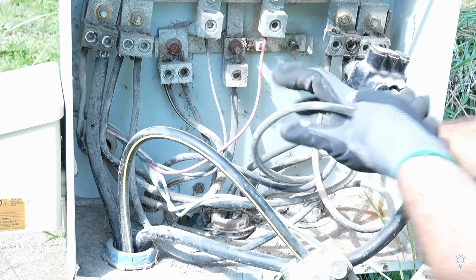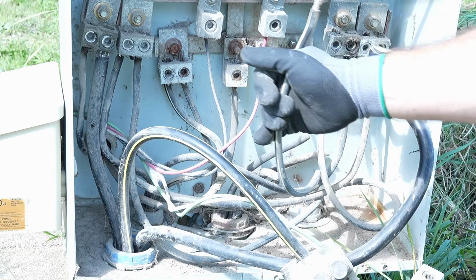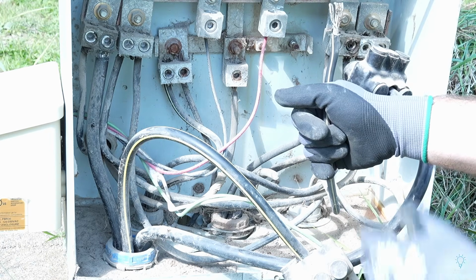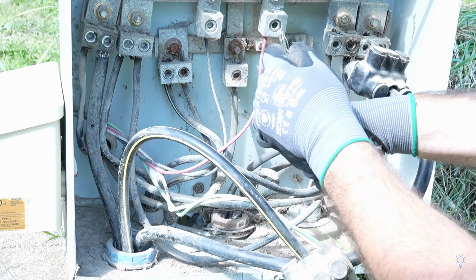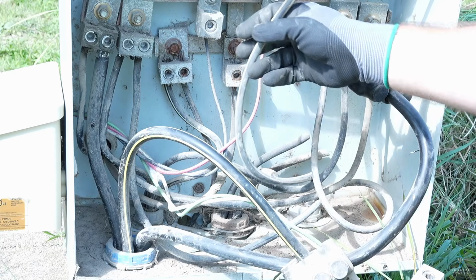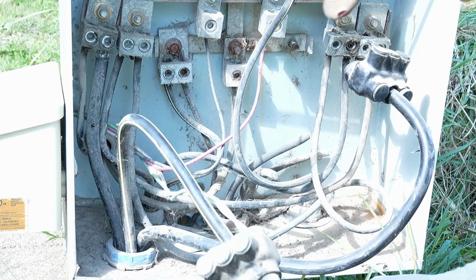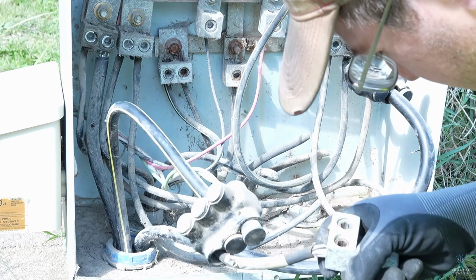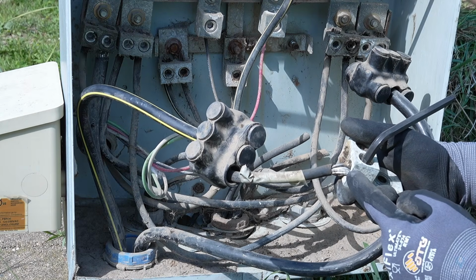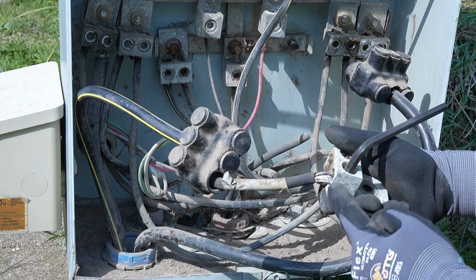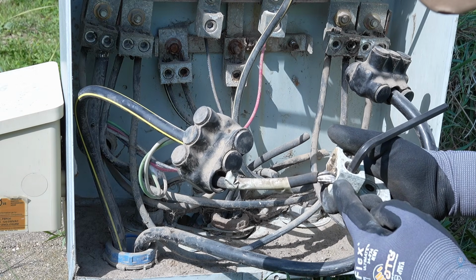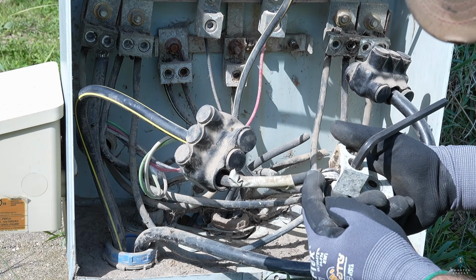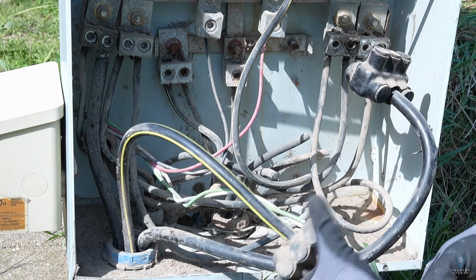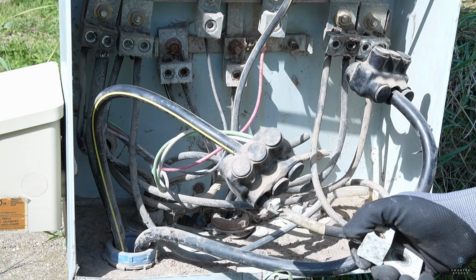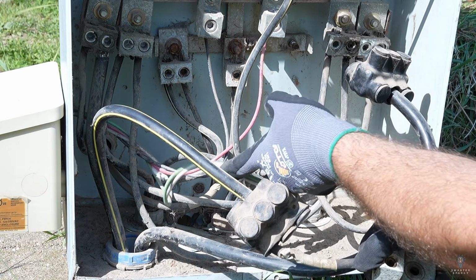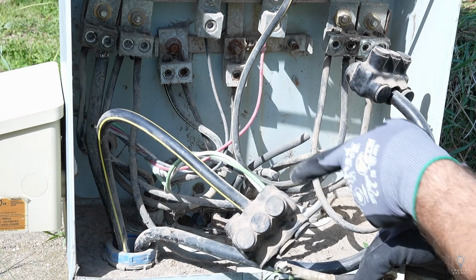So this wire is the neutral for the shop, and it does not look that bad. So that is salvageable. But then we've got this wire going to the house. So I think I'm just gonna cut this wire off flush with where it goes into this lug, and then I'm gonna strip this back a little bit farther, and I'm just gonna leave the Polaris connector there because that is where the neutral for the generator inlet goes.